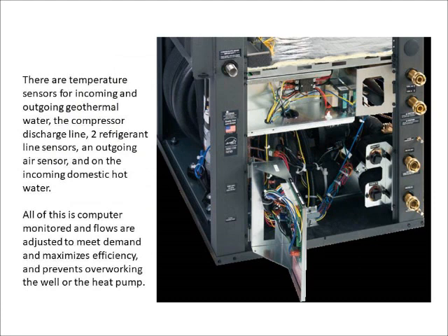There are temperature sensors for incoming and outgoing geothermal water, and also the compressor discharge line. There are two refrigerant line sensors. There's an outgoing air sensor, and there's a sensor on the incoming domestic hot water. All of this is computer monitored, and flows are adjusted to meet demand and maximize efficiency, and to prevent overworking the well or the heat pump.